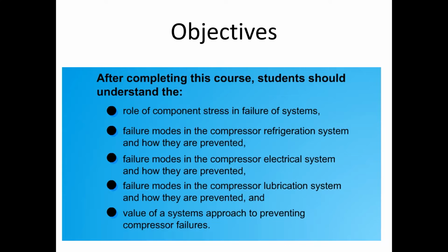So, if you're working on a system and you've had multiple compressor issues or multiple failures, you've got something larger going on than "I keep getting bad compressors," right? That's not your problem. That might be the result, but ultimately the problem isn't, "I don't know why I keep getting all these bad compressors."